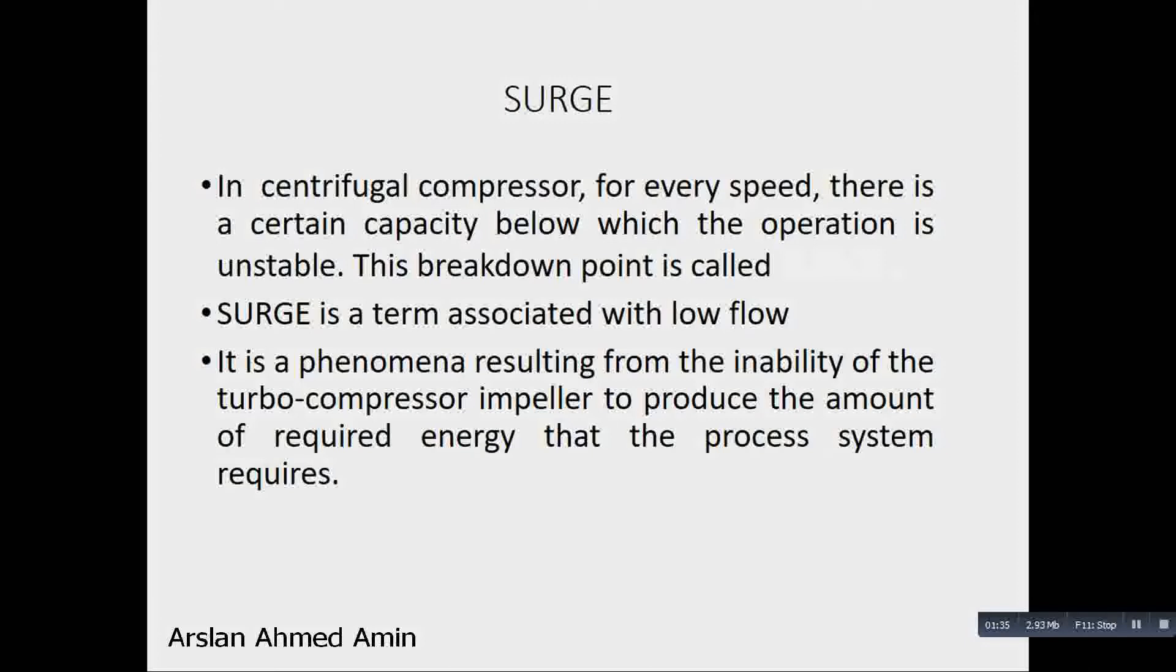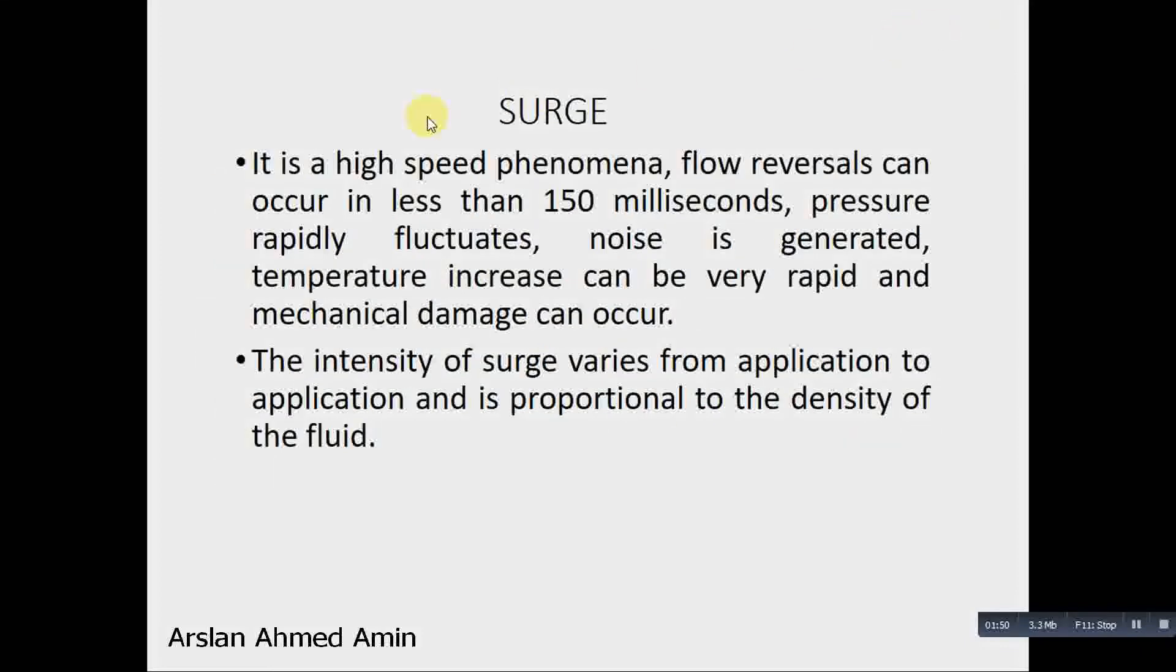It is a phenomenon resulting from the inability of the turbo compressor impeller to produce the amount of energy that the process system requires. We will further see how surge produces. It is a high speed phenomenon. Flow reversals can occur in less than 150 milliseconds.